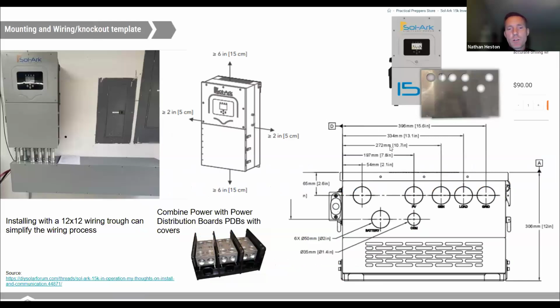So almost every jurisdiction is going to require that rapid shutdown button. It should be a switch mounted on the outside of the house. I encourage the use when you're installing a Sol-Ark 15k of a wiring trough, like as an example here. It might be a 10 by 10 or a 12 by 12 by 48 wiring trough underneath. It does help with wire management. So you can see this one's mounted under these load centers and disconnects that are here. And you can combine inside these wiring troughs with power distribution blocks, etc.